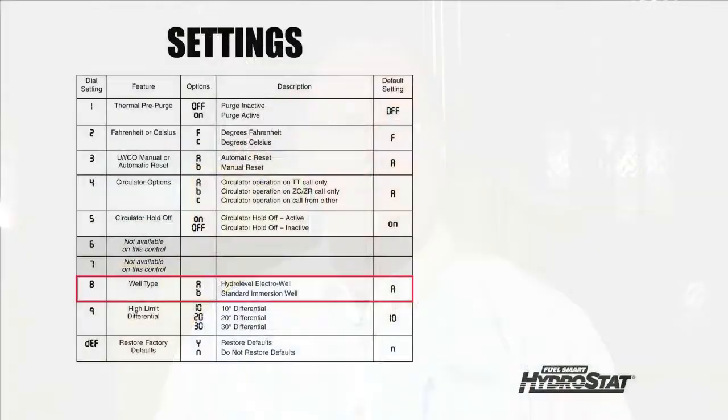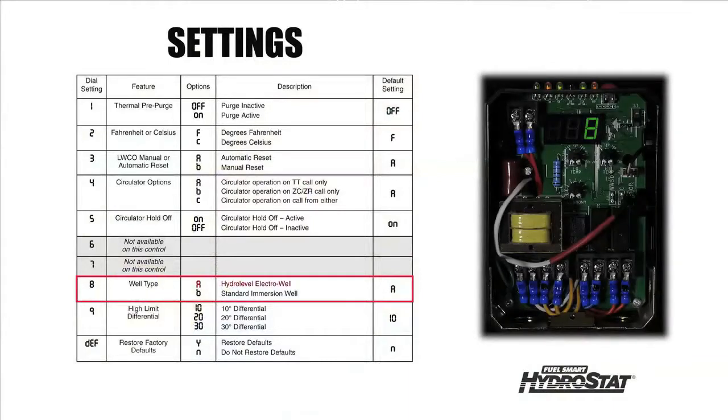If metal to metal contact is ever lost between the sensor and the inside of the well, this option will prevent the possibility of a false low water condition. The default setting A is used for electro wells and B is for standard immersion wells.